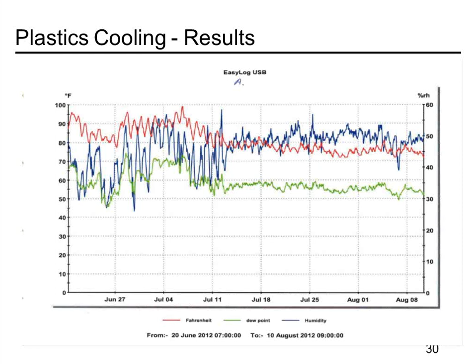On the left, you can see the temperature, the dew point, and the relative humidity prior to our equipment being installed and started. On the right, you can see what we were able to accomplish as far as the dew point and the relative humidity once we had our system up and running. They were able to maintain the dew point between 50 and 60 degrees Fahrenheit, and the temperature somewhere around 80 degrees. The target was about 80 degrees. We averaged a little bit less than 80 degrees over the duration of the project. So we were quantifiably able to achieve their goals, as you can see on this graph here.